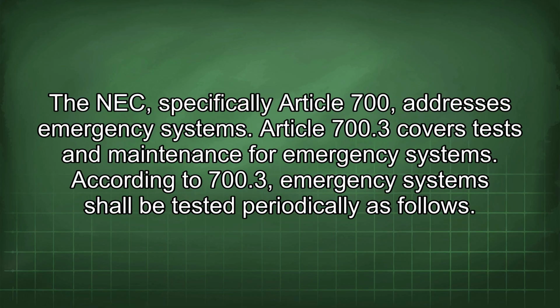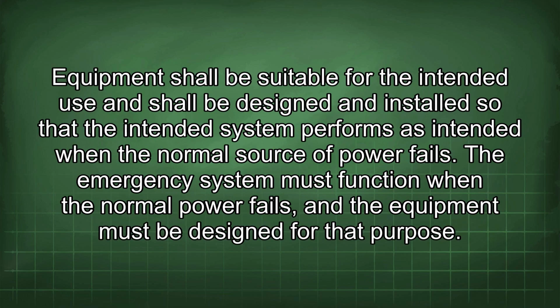The NEC, specifically Article 700, addresses emergency systems. Article 700.3 covers tests and maintenance for emergency systems. According to 700.3, emergency systems shall be tested periodically as follows. Equipment shall be suitable for the intended use and shall be designed and installed so that the intended system performs as intended when the normal source of power fails. The emergency system must function when the normal power fails, and the equipment must be designed for that purpose.